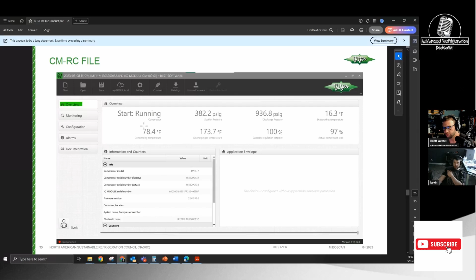Same with the Zero Zone. Zero Zone wires their low pressure switches in per compressor on some stores. Yeah, so it just depends on the manufacturer. For most MT sites, we don't have switchback. It just depends. The Danfoss, it gets hairy doing a switchback.